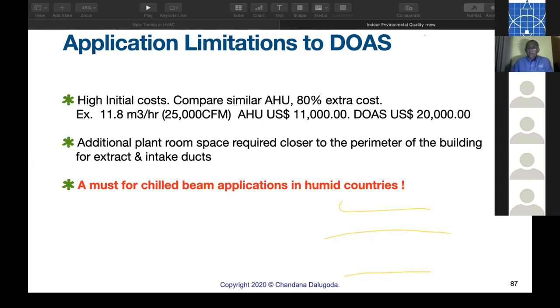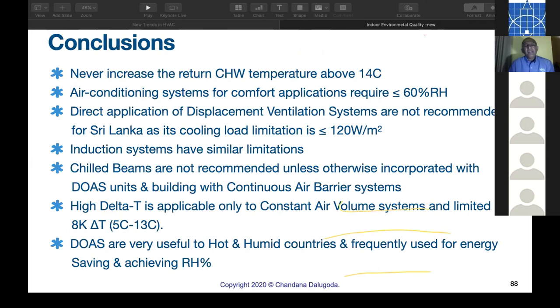So, conclusion: never increase the return chilled water temperature above 14°C. You have drastic problems. So don't act on things preceded by energy saving. First do the comfort air conditioning. With that, do the energy saving. Next, air conditioning system comfort applications require, mind you, below 60% RH.